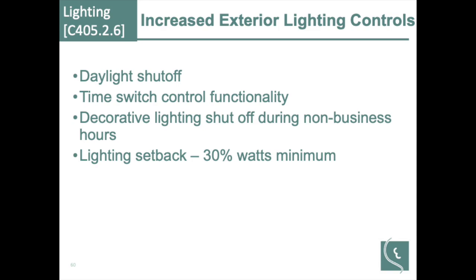But this doesn't necessarily say this has to be done in one control system. So you could have a daylight shut-off photo control in series with the time switch control. So you can have two separate controls provided. It just has both functions have to be there.